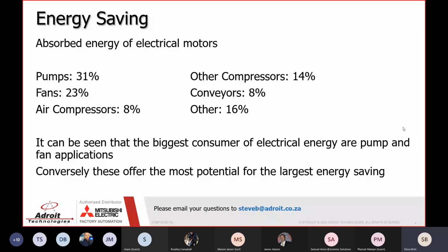Okay, so when we look at energy saving, we can use a VFD to control the speed of a motor and to control how it operates. A survey that was done by a couple of electrical engineers established that the most absorbed energy of electrical motors falls in the following categories. Pumps will absorb 31% of your electrical bill. Fans up to 23%. Air compressors 8%. Other compressors 14%. Conveyors 8%. And other applications up to 16%.